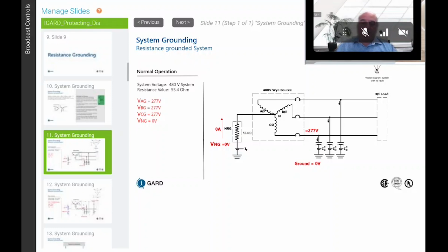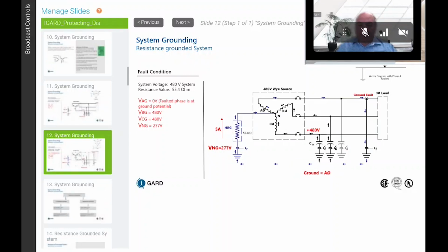When you have a ground fault on an electrical system, that ground fault current has to return back to the source. The only way back to the source is through the resistor. So I'll show you on the next slide. When you have a ground fault, in this case, we've grounded A phase. A phase takes the bonding network all the way back to the ground plane at the source of the transformer, and then goes back to the neutral, and we complete the circuit. So the ground fault is like a switch. You close that switch, you complete the circuit, and the load of that circuit is the resistor. It's the return path for the ground fault current.